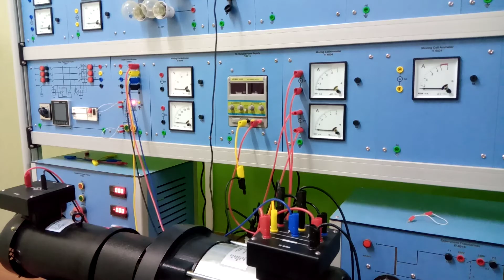Now it's time to connect the three-phase power supply to the power circuit breaker and also to the synchronization indicator. It's very simple - first we will connect this three-phase supply to this power circuit breaker, three phases and neutral, very simple connections. First I will connect the neutral here - here you go. Red phase - okay, this is the red phase.